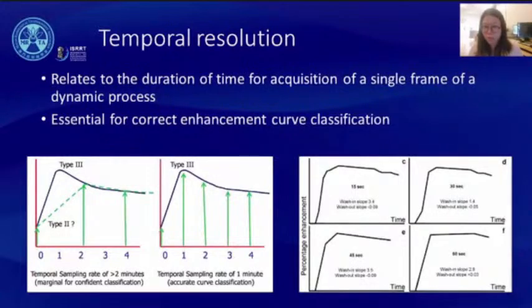And the right image is the kinetic curve of different temporal resolution datasets for the lesions. The kinetic curve shape was washed out for the 15, 30, and 45 second acquisition data, but was plateaued for the 60-second temporal acquisition data, which means that a shorter scan time per sequence provides a better time intensity curve. Temporal resolution is very important in providing a correct enhancement curve classification, which may lead to more accurate categorizing of benign lesions and malignant lesions.